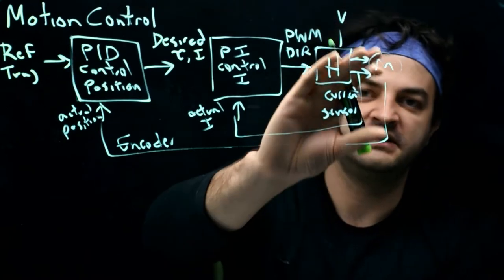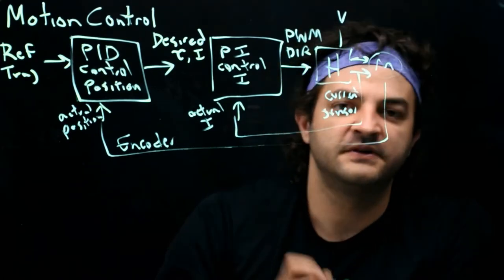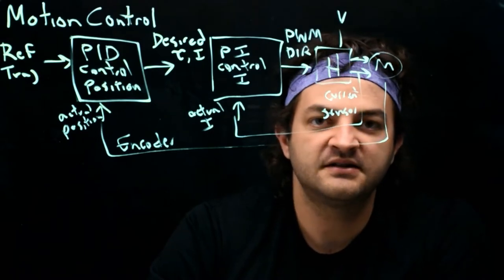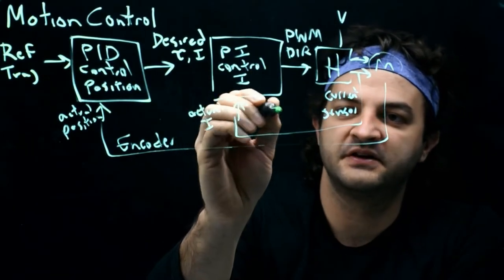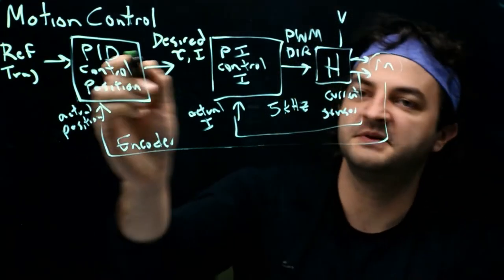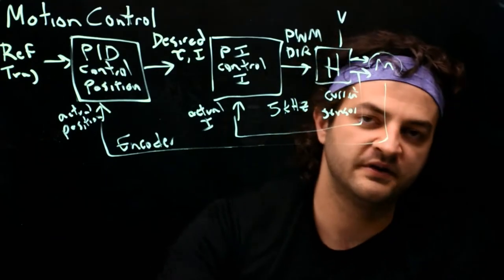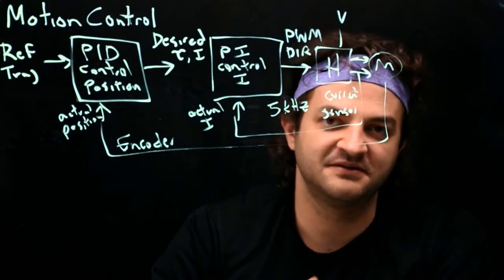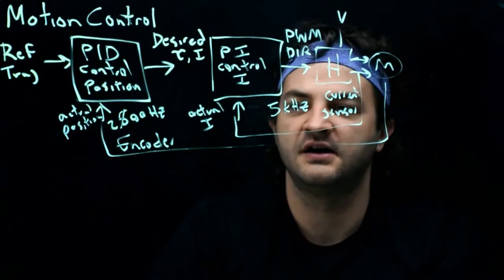The current can change with the electrical time constant of the motor, which is related to resistance and inductance — typically very fast. So we'll do current control at something like 5 kilohertz because the current can change that fast. But the position of the motor can't change nearly that fast. With so much inertia in the motor and load, we don't need to read the encoder 5,000 times a second. Instead, we'll do something like 500 Hz or 200 Hz for position control.